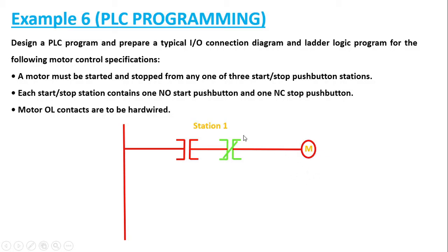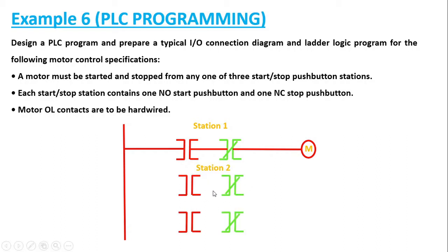Now, the motor must be started or stopped from any one of the three stations — the phrase 'any one' is clearly an indication of OR gate operation. If you've missed the video on how to analyze OR gate operation with respect to PLC, please do watch it. For station 2 and station 3, we will have the same number of contacts. For OR operation, we have to connect them in parallel.